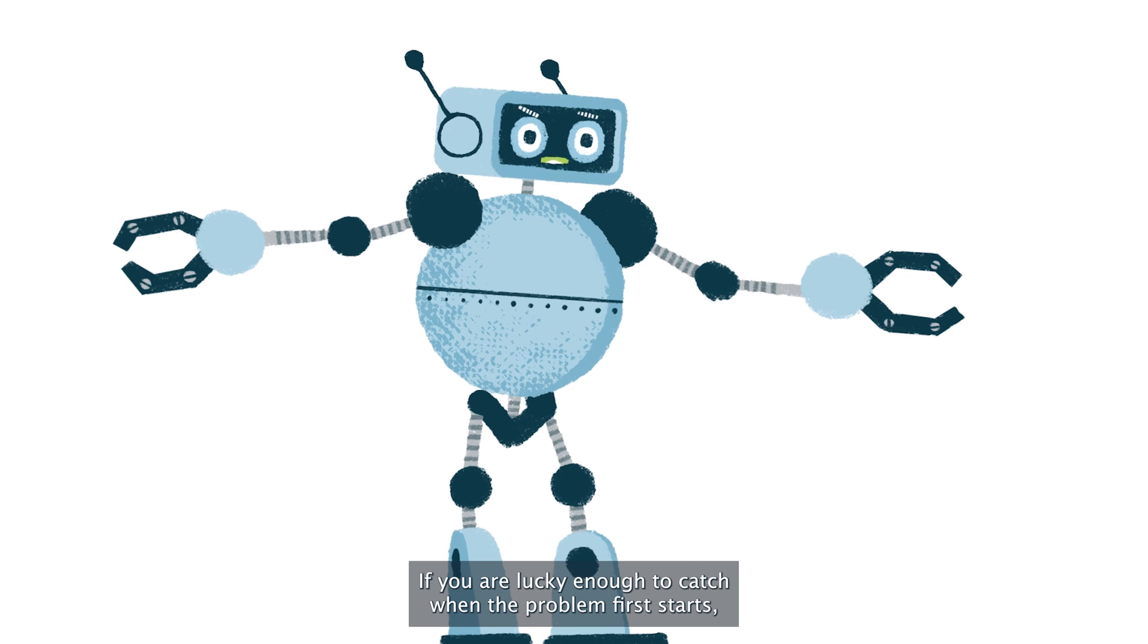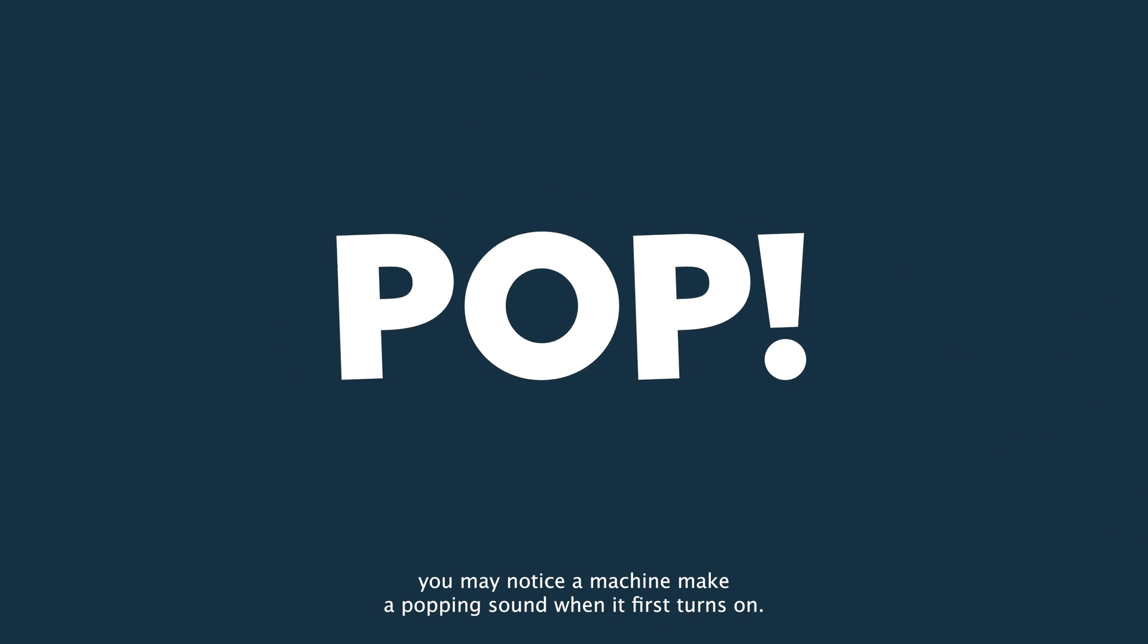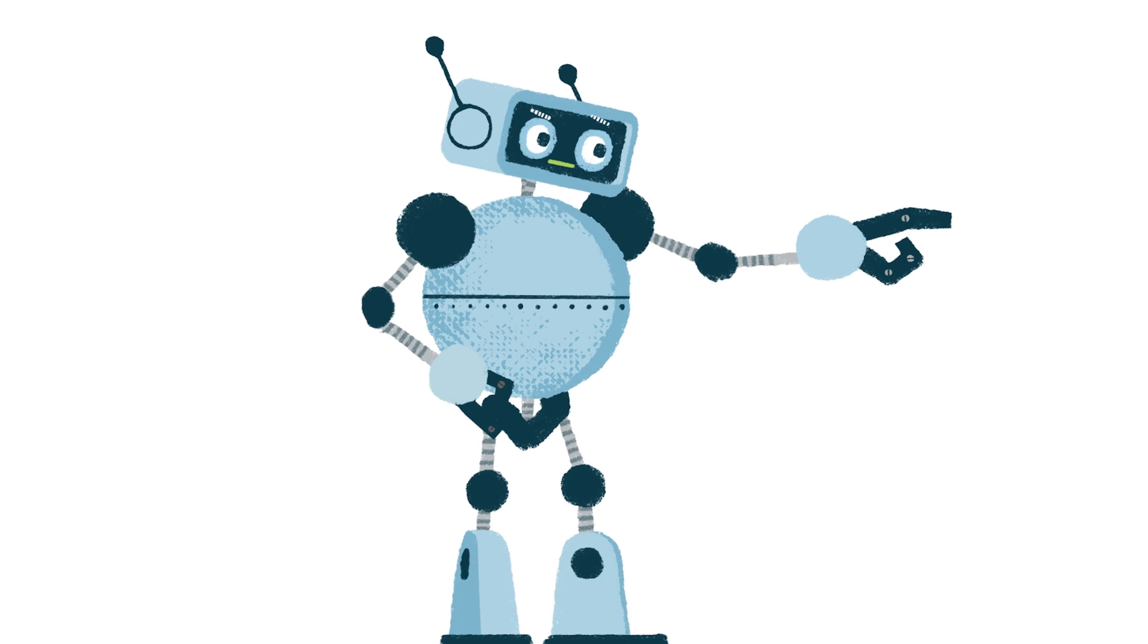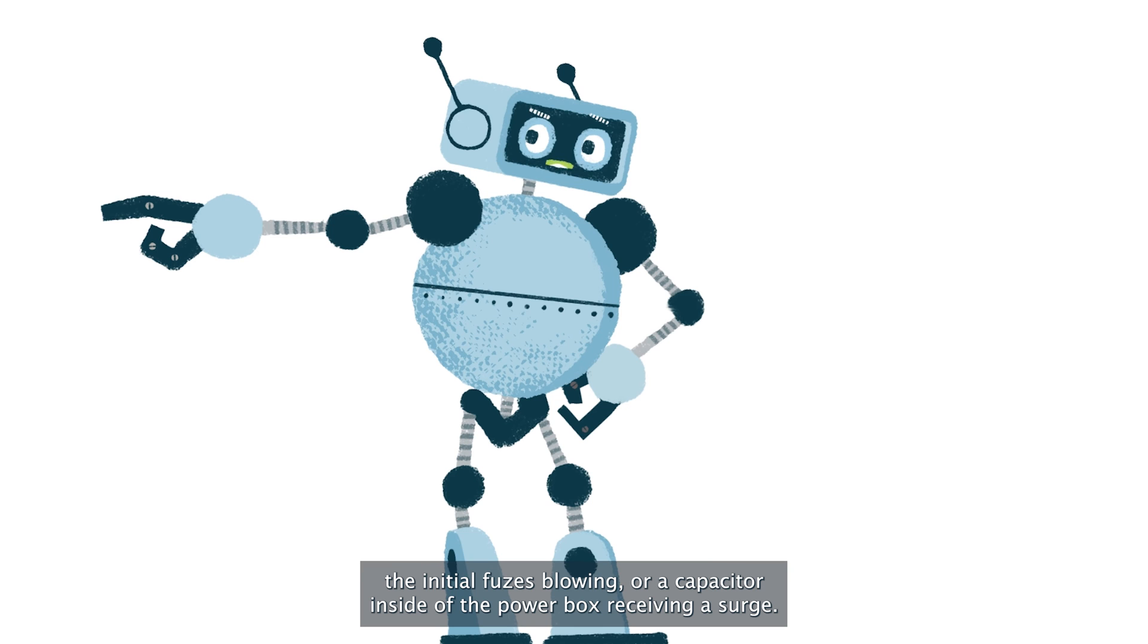If you are lucky enough to catch when the problem first starts, you may notice a machine make a popping sound when it first turns on. This may be a poor connection leading to an electrical arc, the initial fuses blowing, or a capacitor inside of the power box receiving a surge.